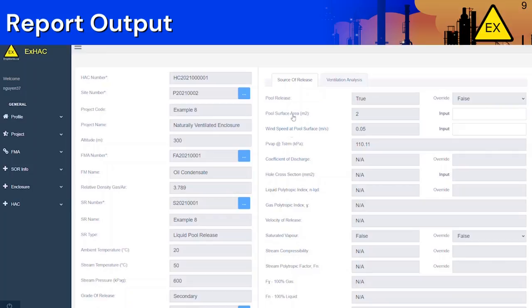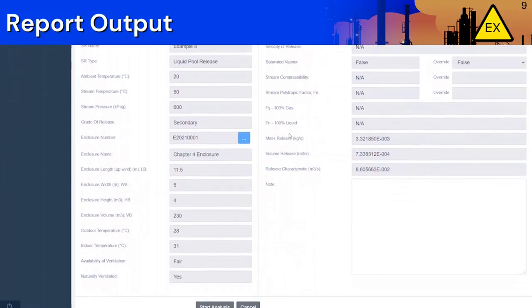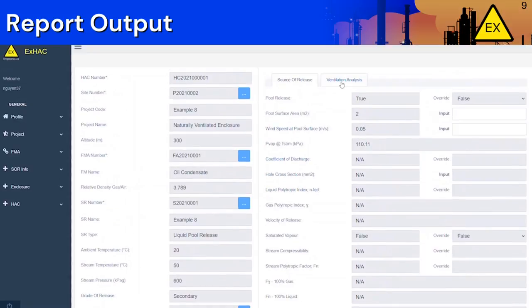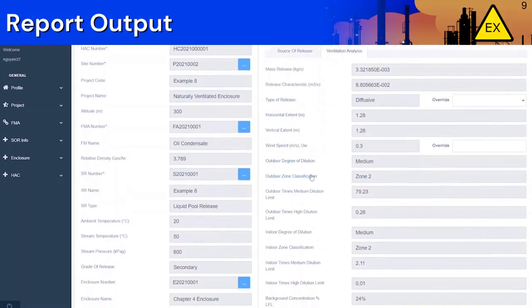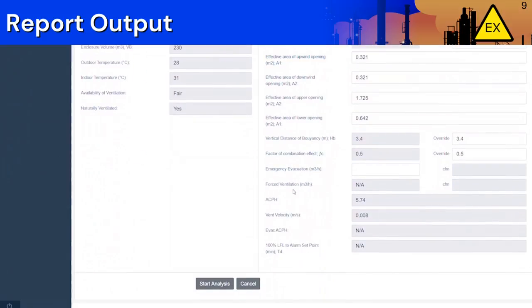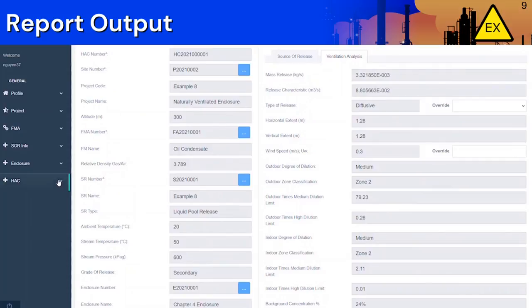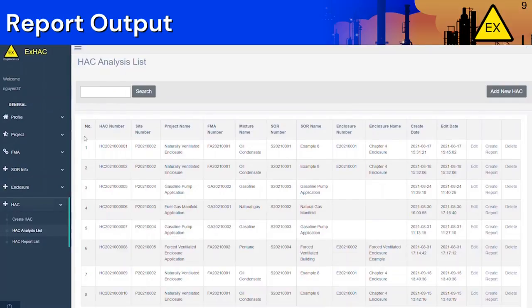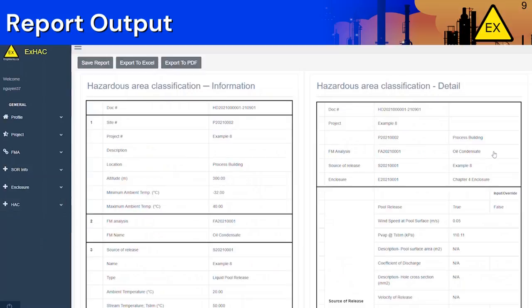The results will be displayed on the Source of Release and Ventilation Analysis tabs. The Source of Release tab will indicate the mass and volume release rates and the release characteristic. The Ventilation Analysis tab will indicate the zone classification and extent as well as other key parameters such as ventilation rates and velocities. If you are satisfied with the results and wish to create a report, go to the HAC Analysis List, find your HAC analysis row, and click on Create Report. You will also be able to save the report and export it to an Excel or PDF format.